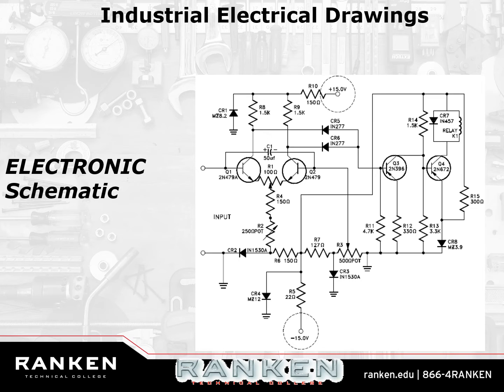You're going to think, I better know which one it is. You're going to pop it out of there. You're going to pop a new I/O board in there, and it starts lighting up. Fixed it. I'll be in my office if anybody needs me. You're going to walk away like a friggin' wizard because you identified the one board that didn't have any LEDs on it. But that's about 50% of your job.